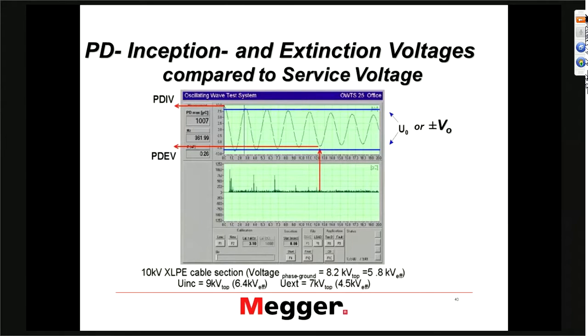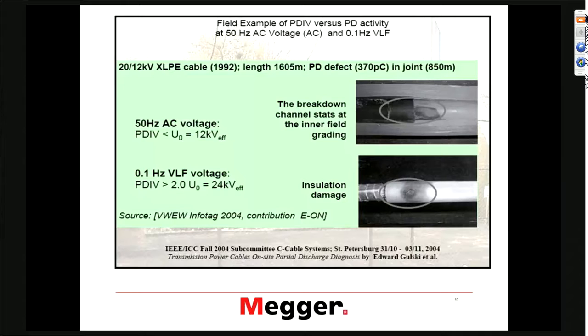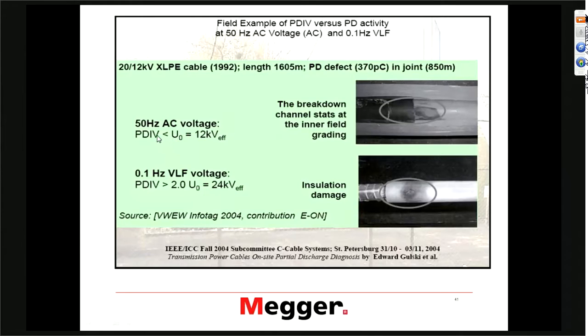There are some positives for online testing as well. It all depends on what the objective is — what you'd like to learn about the cable condition and the cable health — that determines what type of test method you use. Here is just a quick slide to show the same splice tested at 50 Hz power frequency PD test versus 0.1 Hz PD test, and you can see the inception voltage is substantially different — more than two times. At 50 Hz it shows less than operating voltage, so you should be concerned, whereas if you run the same test on the same splice at 0.1 Hz, you would get a much higher result — double the operating voltage — which would tell you you don't have to be concerned.